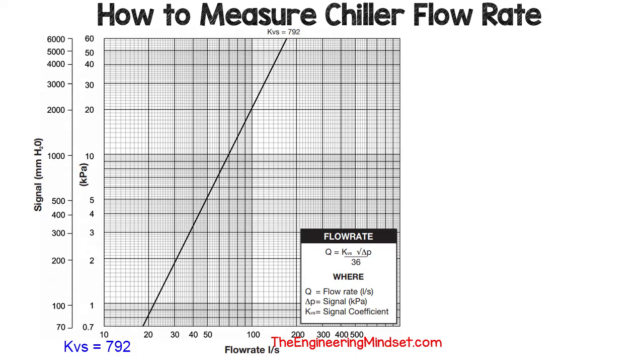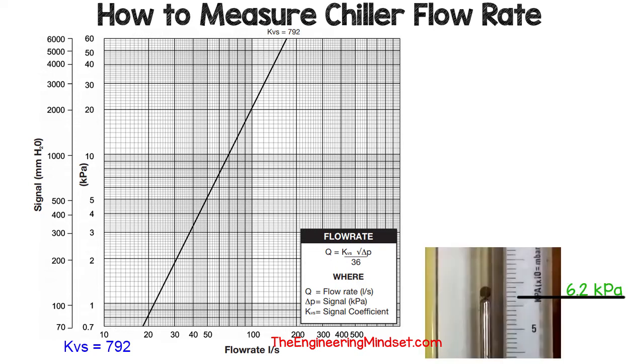The manufacturer will usually also provide a chart so you can perform a quick lookup. Mark our reading on the chart — which was 6.2 kilopascals — on the y-axis, then draw a horizontal line across until it hits the KVS line. From there, draw a line vertically downward to read off the flow rate. Here you can see it gives a flow rate of around 55 litres per second.